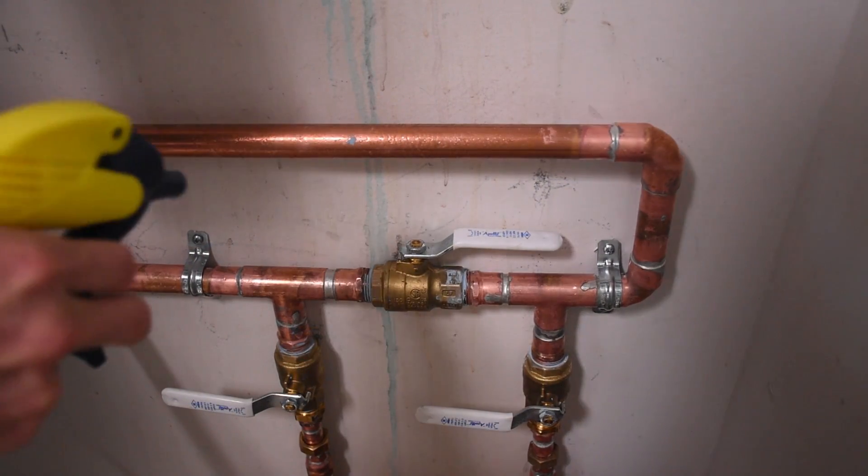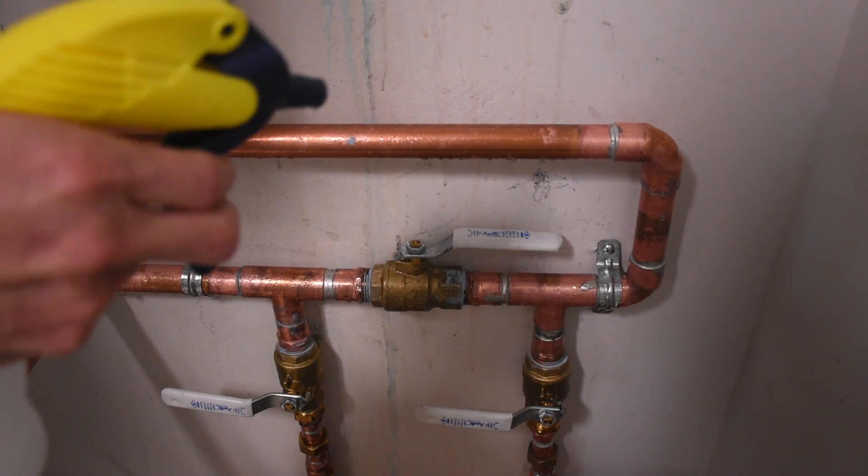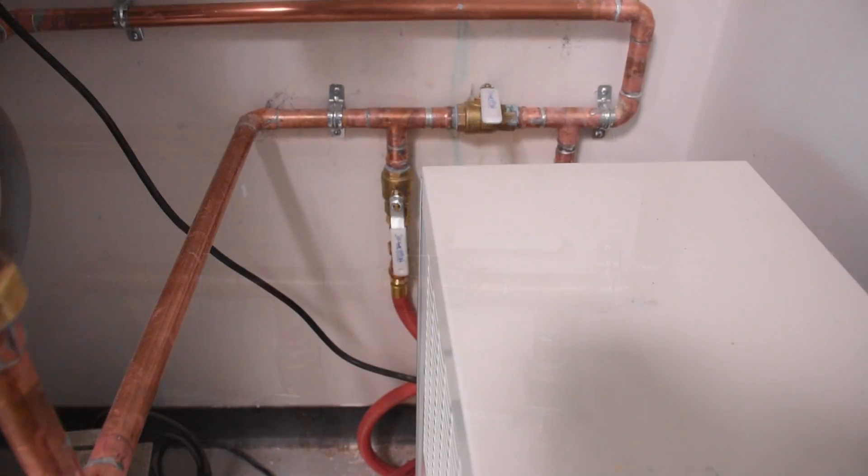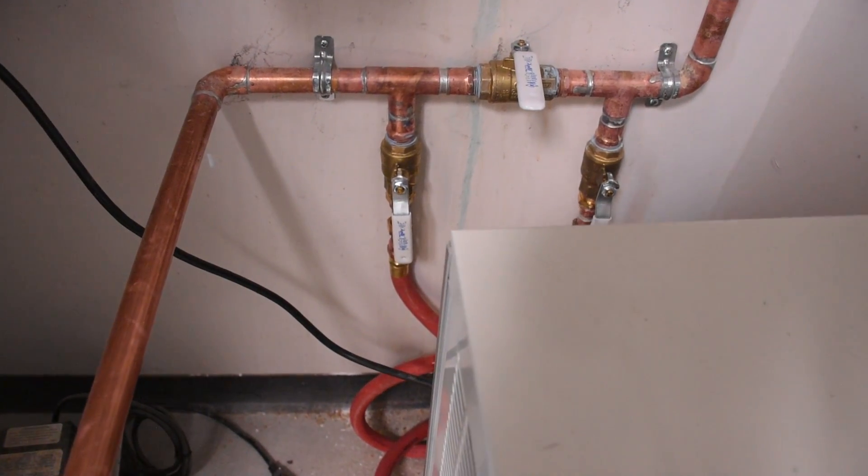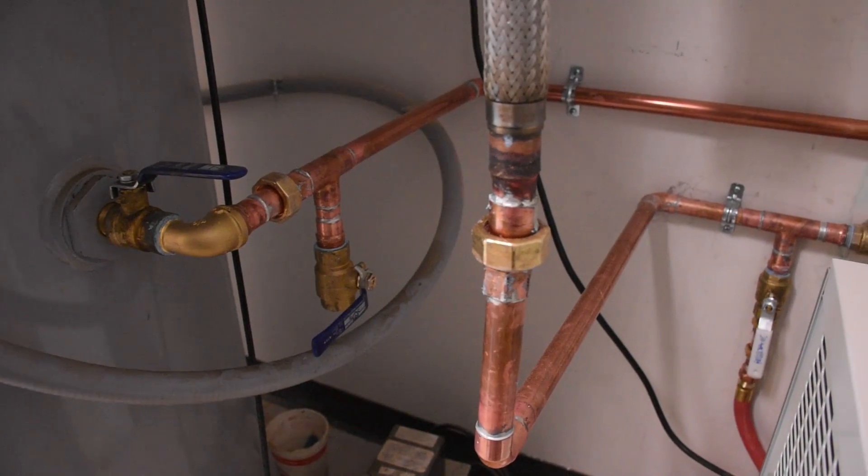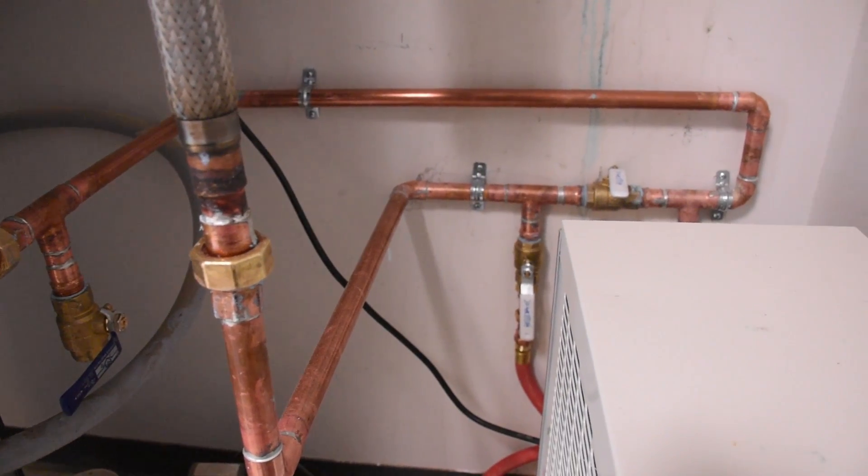Now that it's in place, a quick shot of soapy water will allow me to see any bubbling leaks. And there aren't any. There were 30 soldered connections in all and no rework was necessary due to all the time I spent doing pipe math. I actually think it looks better than the pro job that I attached it to and I'm quite proud of myself.